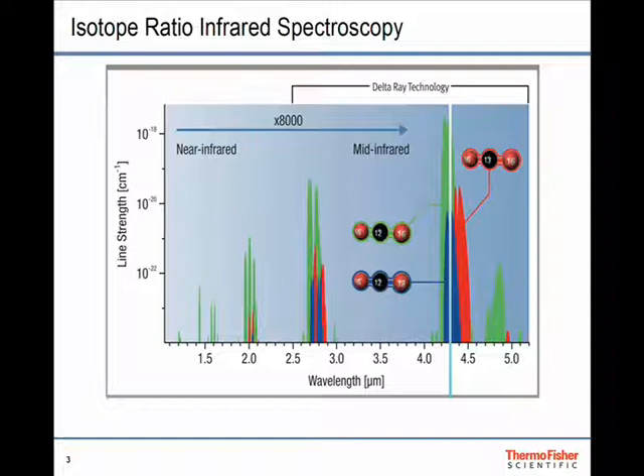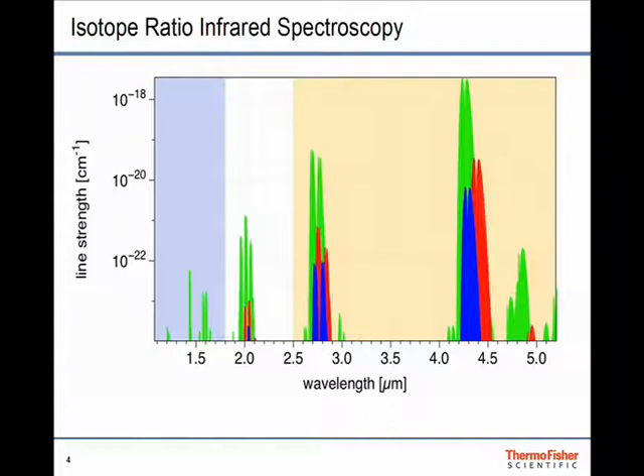Another thing to notice is that in the mid-infrared, you have about 8,000 times stronger lines than at 1.6 micron, a commonly used wavelength for these measurements. Now, what looks like bands are actually hundreds and hundreds of individual lines due to quantum mechanics. These rotational and vibrational states of the molecule that create the absorption are quantized. Now I'll try to zoom in so you can see how this looks. You start seeing individual transitions. We keep zooming in more to about the range that one individual laser scan can cover. You have a tunable diode laser that can cover these lines. You can get 13C, 18O, and the 12C lines in one laser scan. That's fundamentally how it works.